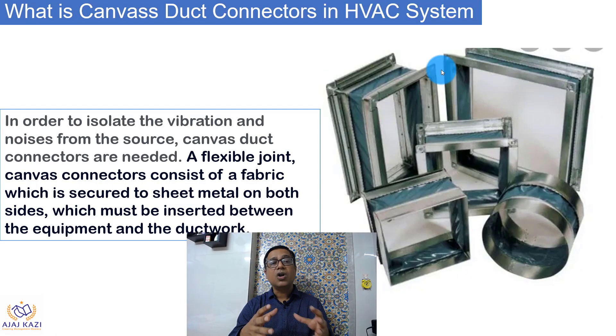In order to isolate or minimize the vibration and noise from the source — the source being the equipment — flexible joints or flexible duct connectors are used. This is the fabric which is connected to sheet metals from the both side, which can be connected to an equipment from one side, while the other side is used to connect the ducts.